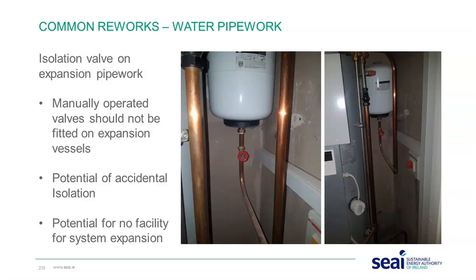We ask that no manual valves are fitted. There is potential for accidental isolation. I've had it myself in the past where I've seen people turn valves off and forget to turn them back on. They might have a cistern overflowing on the WC or something like that, and they forget to turn it back on. They think everything's working, and the system has no expansion and the safety valve blows off.